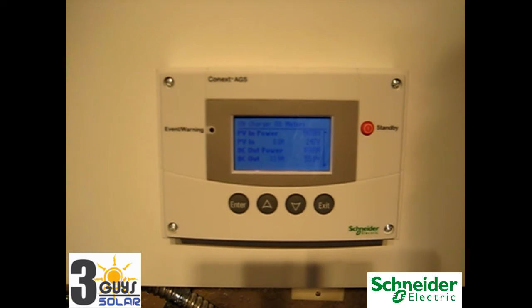The reason that the amperage on the output, in this case, is 40 amps and the input is 8 amps is because of the voltage difference. The PV input voltage is much higher, so the amperage is lower. As the voltage is lowered from 250 volts down to 50 volts, the voltage is lower but the amperage is higher. Volts times amps equals our watts.